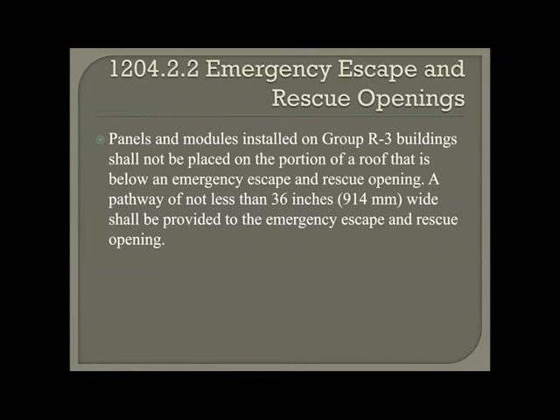Okay, here's a picture of one that was installed at 33rd and Huntington. This is an apartment building, which is classified as R2. Again, information where you're kind of going, what? But the panels stop somewhere over here by the tree, so they knew that they weren't going to be blocked. This is on the south side of the structure. The structure's on the north side of the street, but we can get access here. There's nothing on the back side of the building where we can still get access. So even though it doesn't necessarily meet some of the requirements we're going to cover a little bit more, we still have all the access we probably need in order to address this. And then there's another exception to the codes that allows us to say, hey, this works for us, based upon the roof design of an apartment complex like this. But that's something you can ask us ahead of time. We can help lay that out.